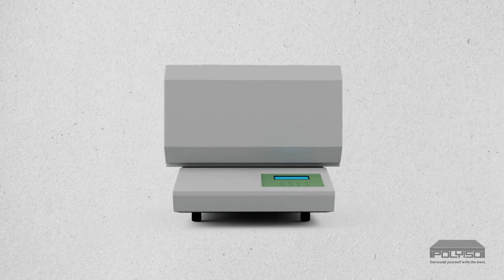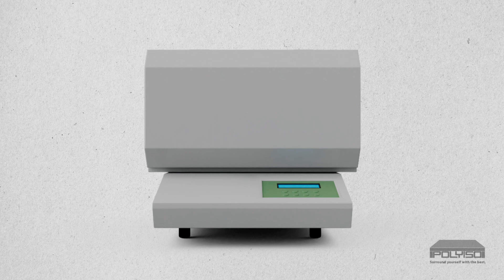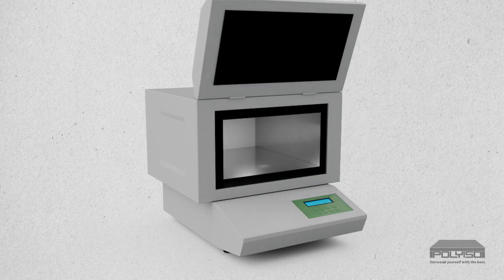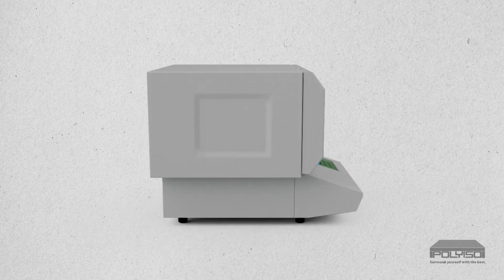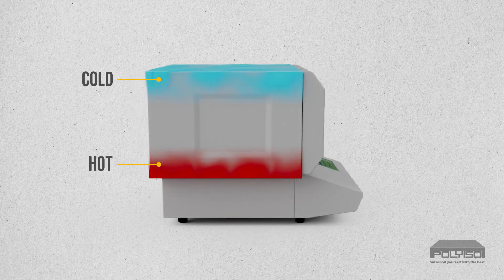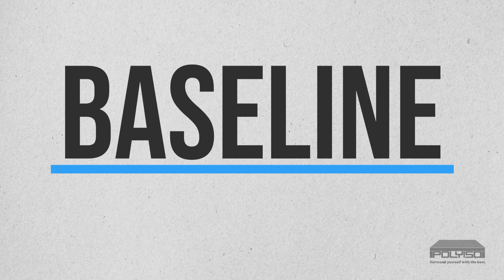Let us look at how the R-value test is conducted and the role mean temperature plays in the testing. Third-party accredited laboratories use an instrument called a heat flow meter to measure heat flow through the product. The heat flow meter is an instrumented box that exposes the insulation sample to a temperature differential on the top and bottom surfaces of the sample — one hot and one cold. The difference between the hot and cold surfaces establishes the mean temperature for the R-value measurement.